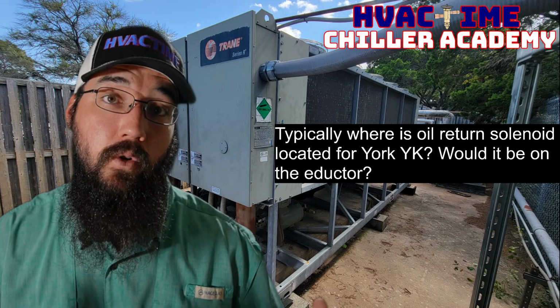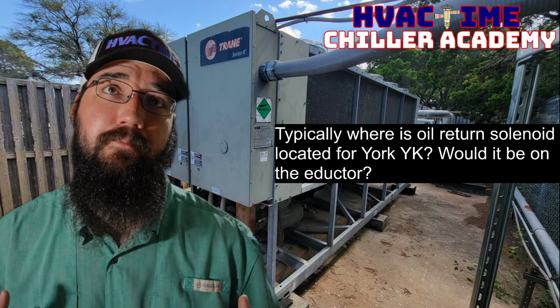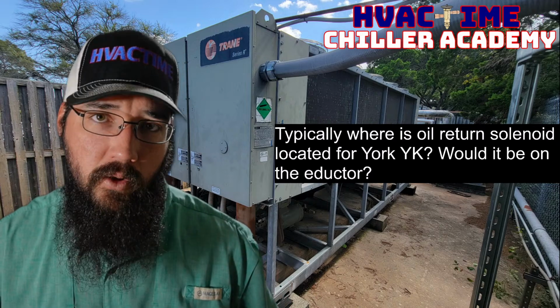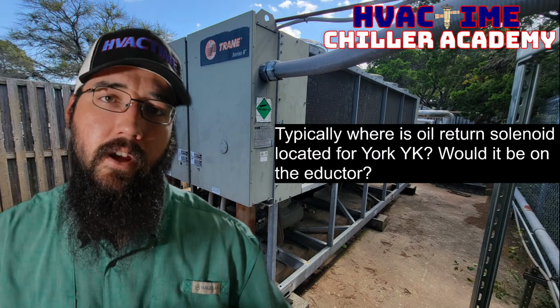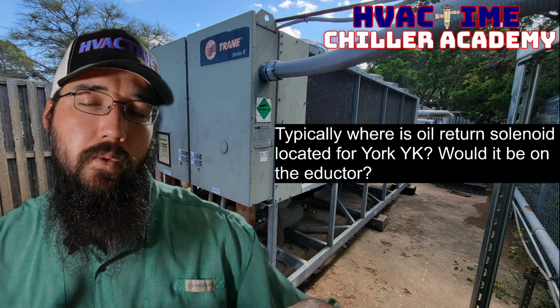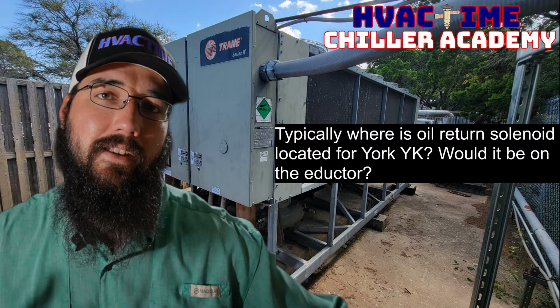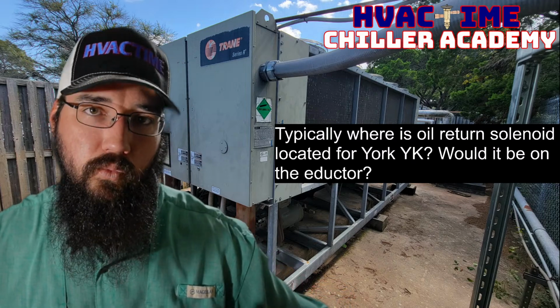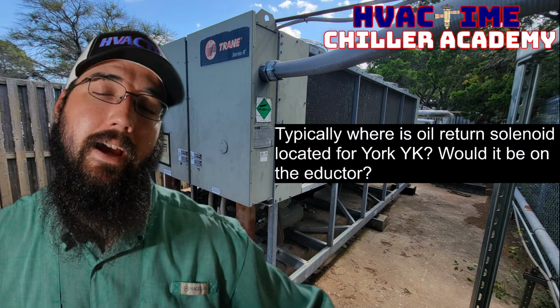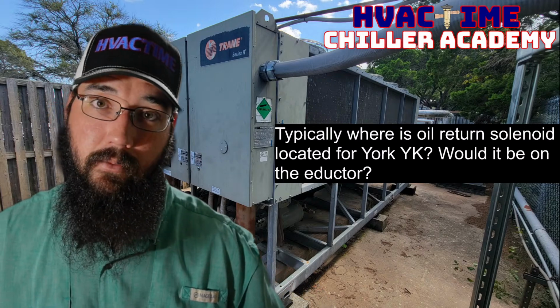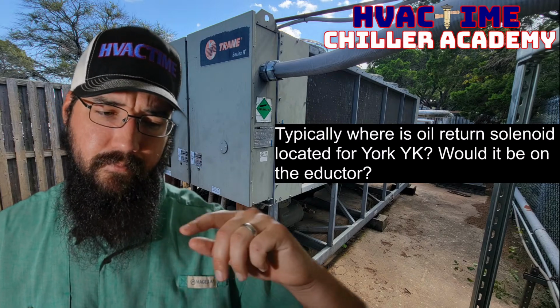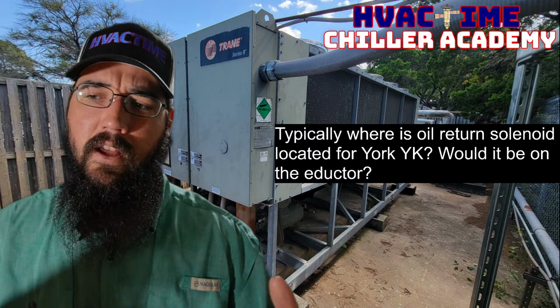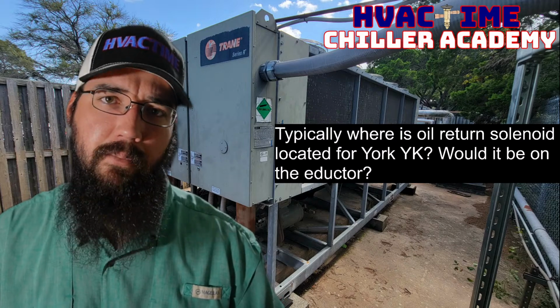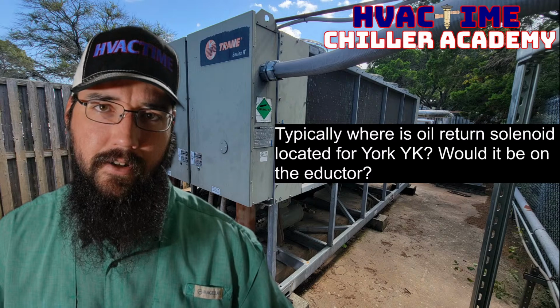And that is where you want your eductor to be pulling from. So if you're running too low of a liquid level on your evaporator, you'll start to push down, and you won't have as much success getting that oil-laden liquid refrigerant to pull back into the eductor assembly. So that's something to be aware of. Be very careful of that, which could then lead to, you've already got a low level in your evaporator, which is going to impact its operation and efficiency.